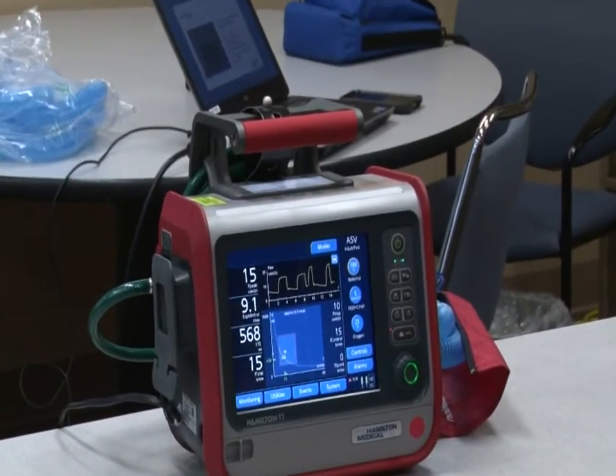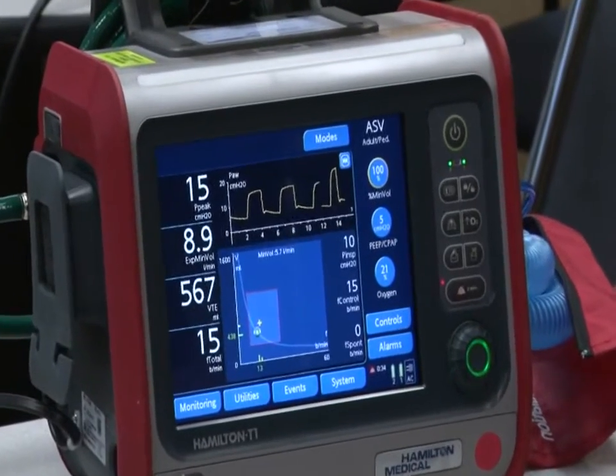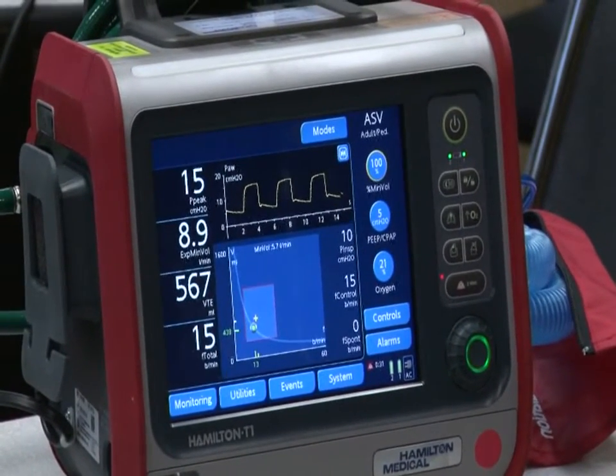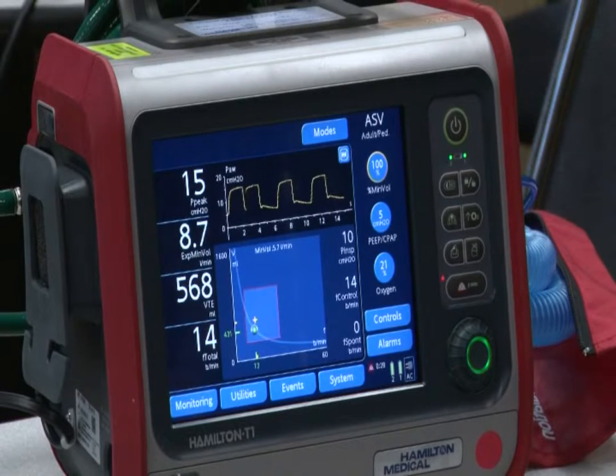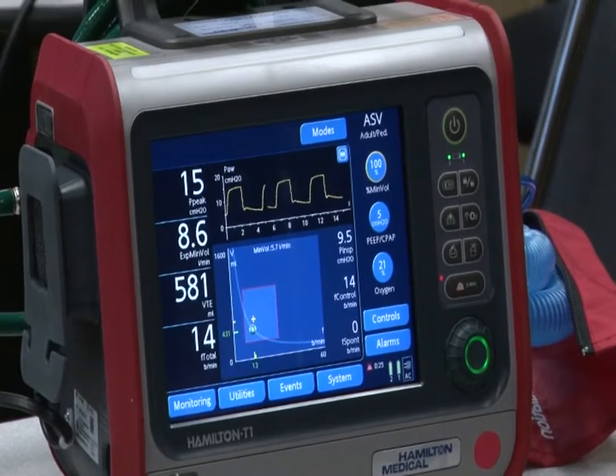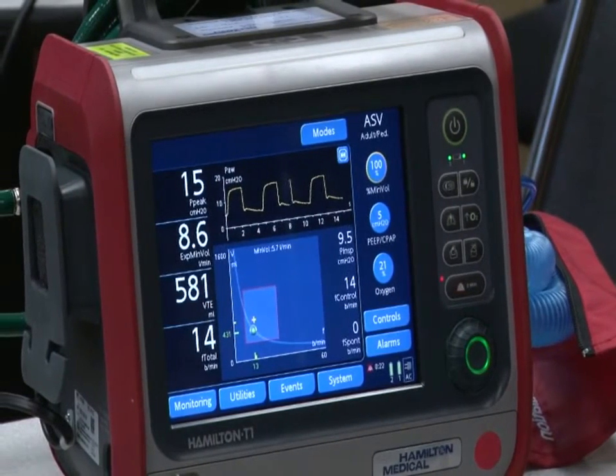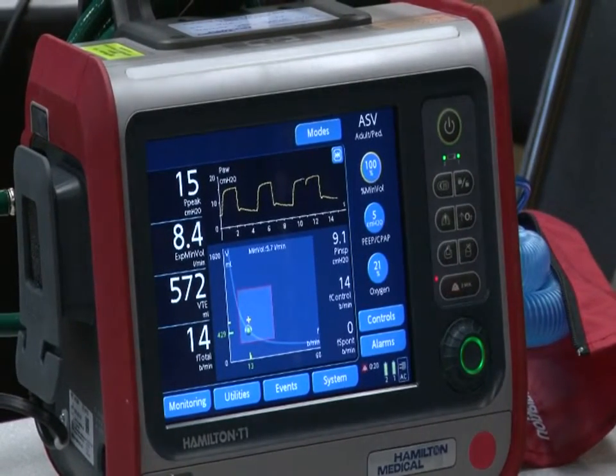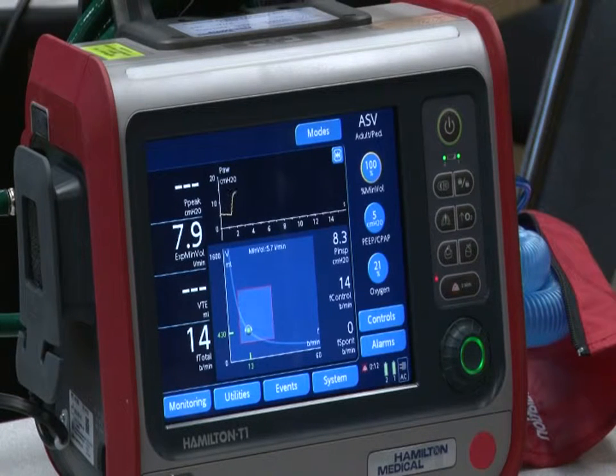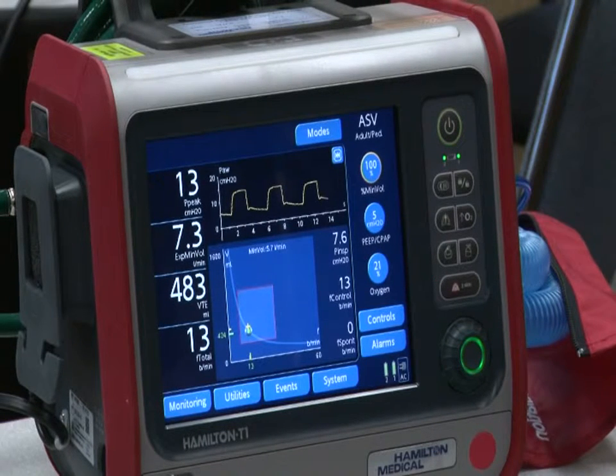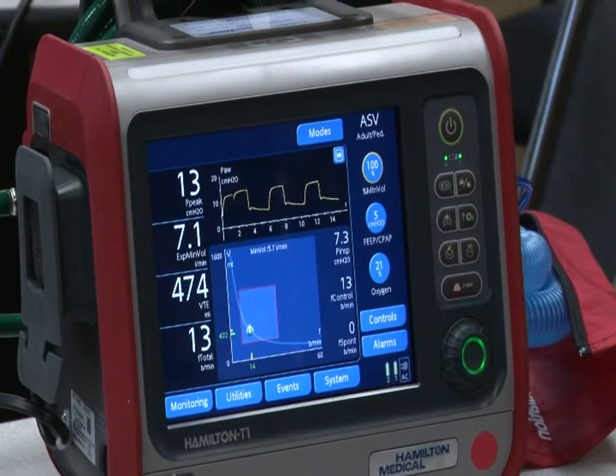The reason for that is that in the initial 3 to 5 breaths that the patient is receiving from the T1, or any ventilator that has ASV on it for that matter, which is all of our ventilators, it's a little bit like turning on the shower, right? Do you turn the shower on and just jump in? No, you put your hand or your foot in to see whether you're going to be scalded or frozen to death before you get in, and you make an adjustment. So those first 3 to 5 breaths are the ventilator basically testing the patient, learning the patient's pulmonary mechanics. And that's typically going to be somewhere around 15 centimeters of water. Thereafter, the ventilator is going to present a few additional things, populate that display.